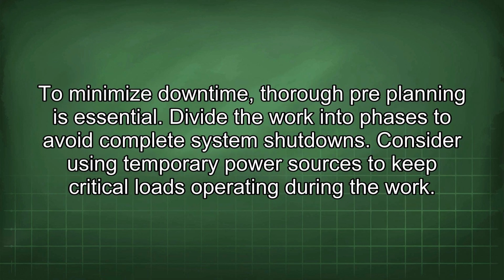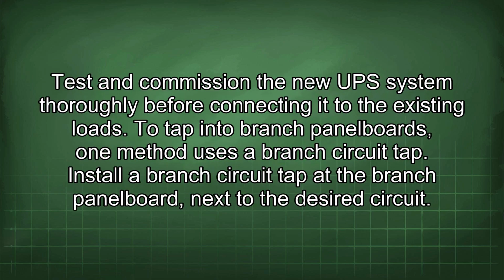To minimize downtime, thorough pre-planning is essential. Divide the work into phases to avoid complete system shutdowns. Consider using temporary power sources to keep critical loads operating during the work. Test and commission the new UPS system thoroughly before connecting it to the existing loads.